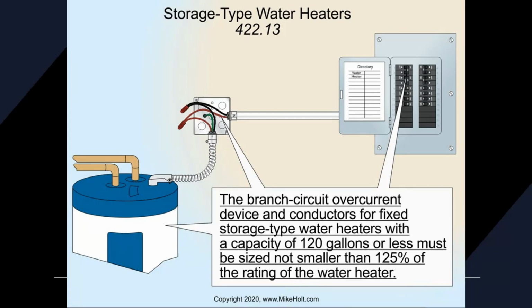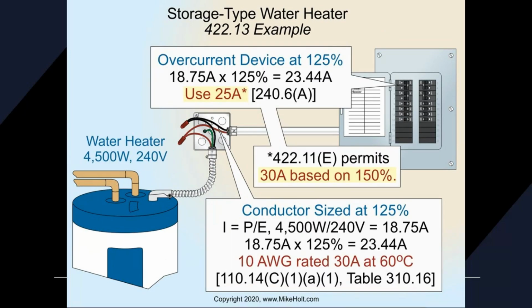So the branch circuit overcurrent device and conductors for fixed storage type water heaters with a capacity of 120 gallons or less must be sized not smaller than 125% of the rating of the water heater. So the breaker has to be 125% of the water heater. Just so you are aware, if you're not aware it exists, it's a real easy way to get a question wrong on a test. So think about water heaters. Think about adding 125%.